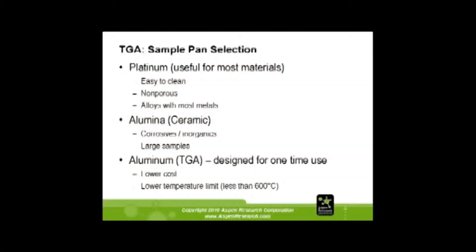Platinum is the pan I use most — it is very easy to clean. The only thing is it does alloy with most metals. So if you use a tin-lead solder and want to measure the melting point, you'll ruin the platinum pan because it ain't coming off. For metals, I would probably use the ceramics — at least you can get the sample out. Ceramics are great for corrosive, inorganic, and high-temperature samples. They do make TGA pans in aluminum, but they are only good up to 600 degrees before the pan will melt. Aluminum pans are usually one-time use but reasonably priced.